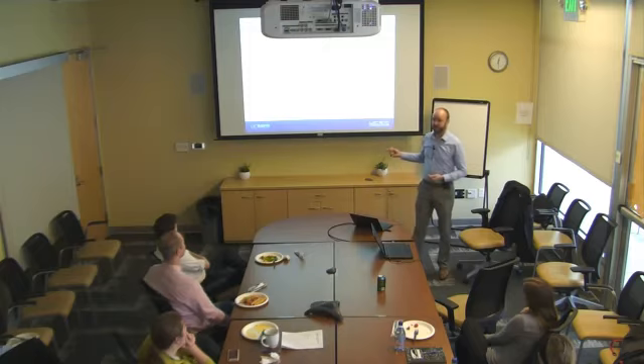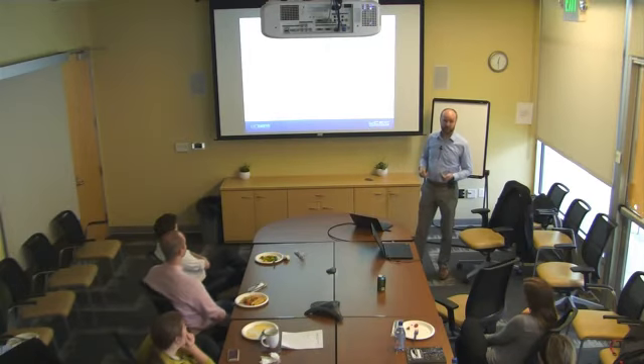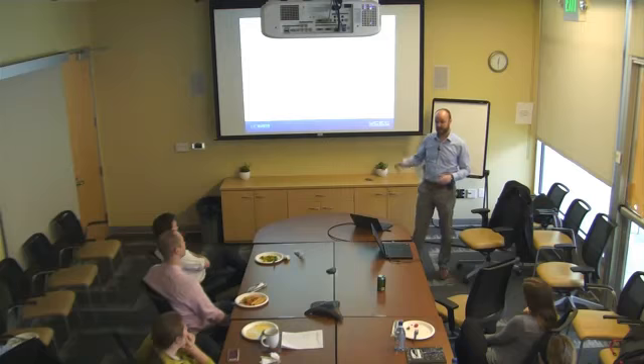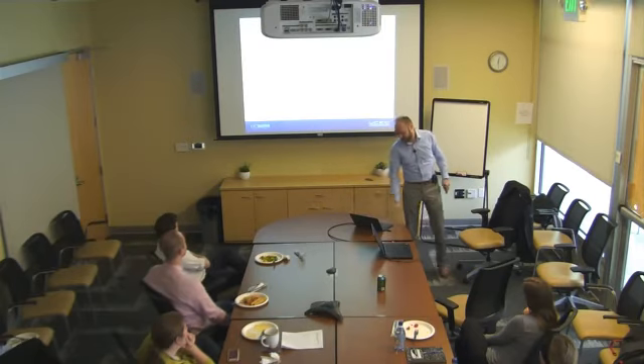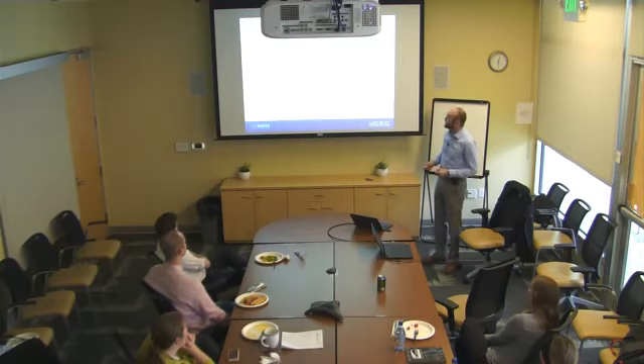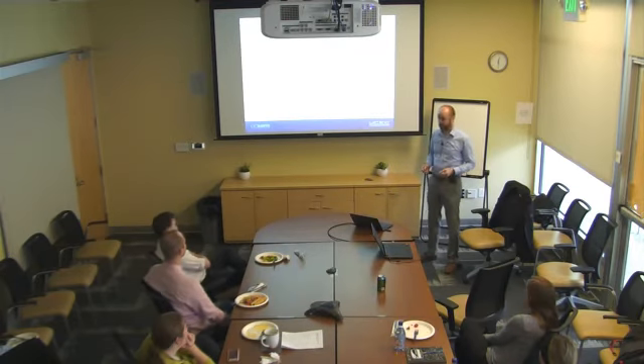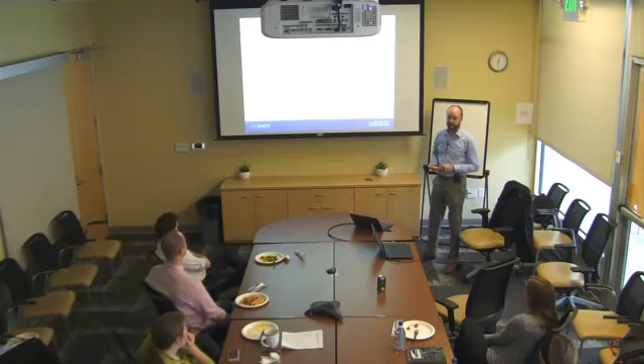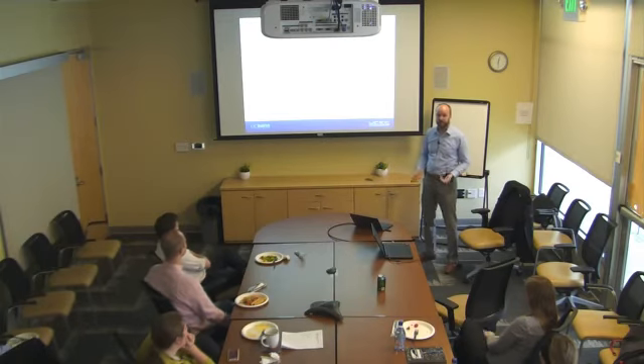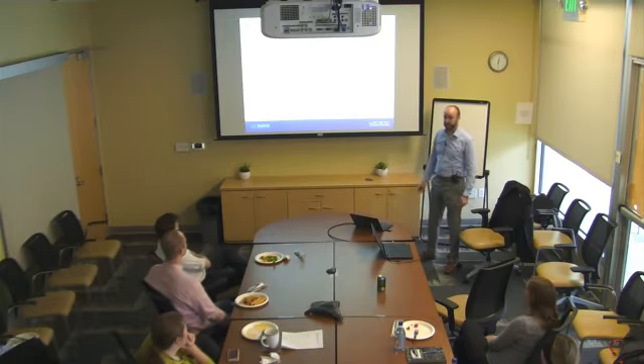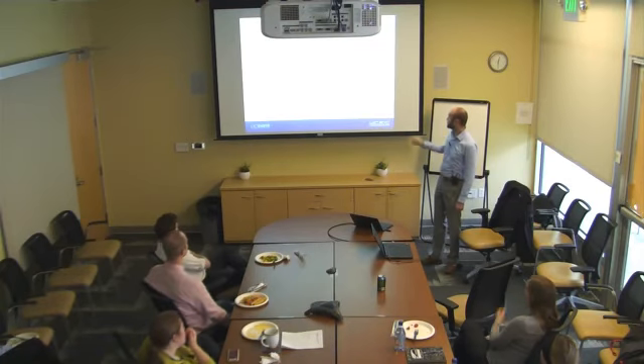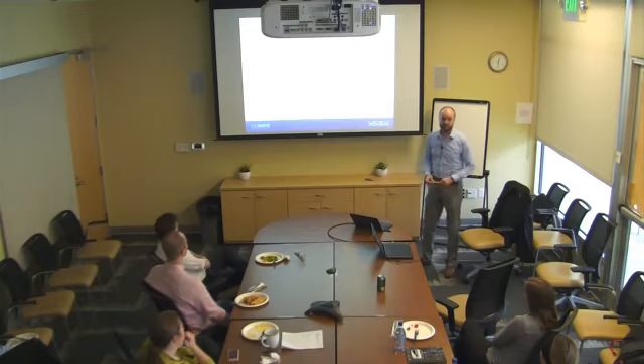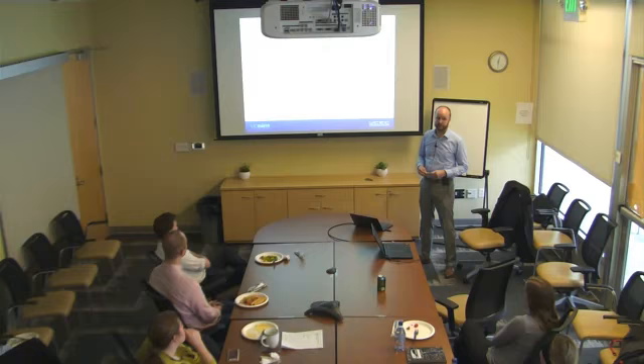You essentially can control the water coming from the water tower. You control that temperature to simulate a peak event in order to create a map of how the system would perform at high outdoor air temperatures. And in summary, thermal energy storage systems, their capacity to offset load is largely affected by the ambient conditions. And the current 10-day average baseline system and the permanent load shift methods for evaluating the systems basically prevent them from being financially incentivized because they're not properly predicting their value. And like I said, the error is as much as 28% for the permanent load shift program when the TMY3 data is used instead of the ASHRAE 1 in 10.